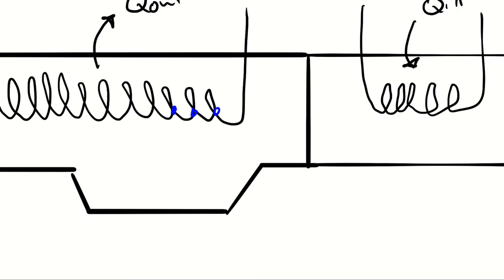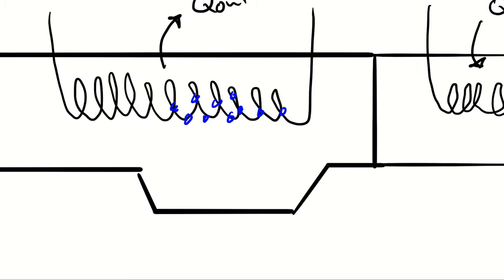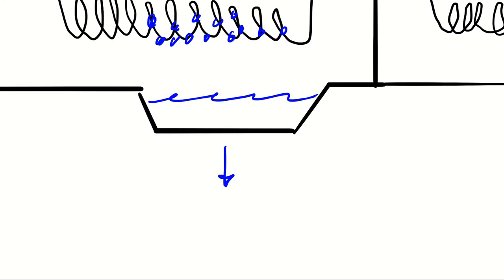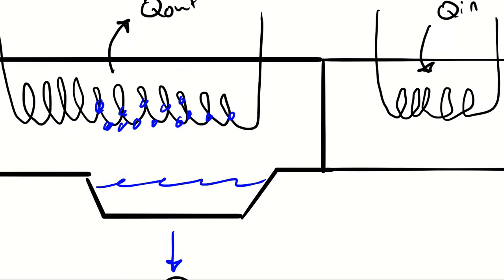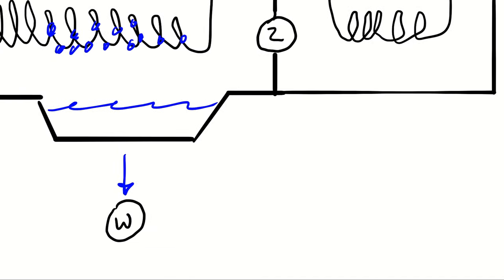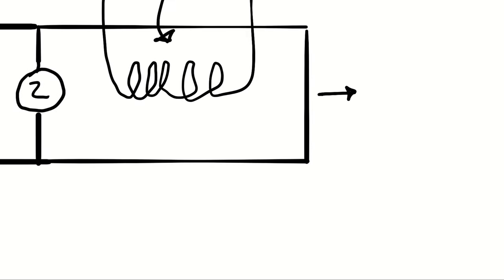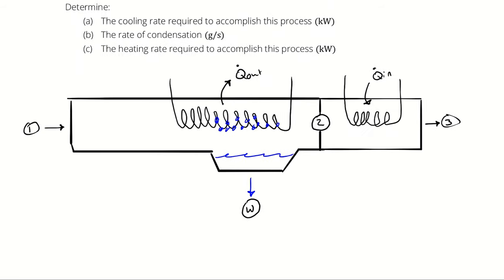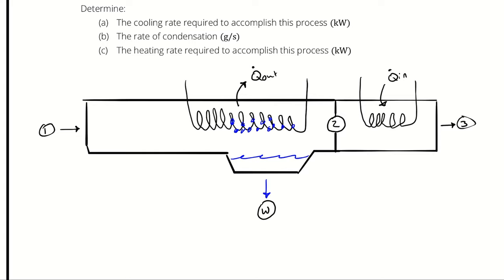Water gathers on the cooling coils as a result of the condensation process — a lot of water, in fact — and it leaves down here. I'll call that state W. I'll establish a state point between the cooling and heating processes: that's state point 2. Egress is state point 3 and ingress is state point 1. So we have cooling with dehumidification from 1 to 2, and then heating from 2 to 3.